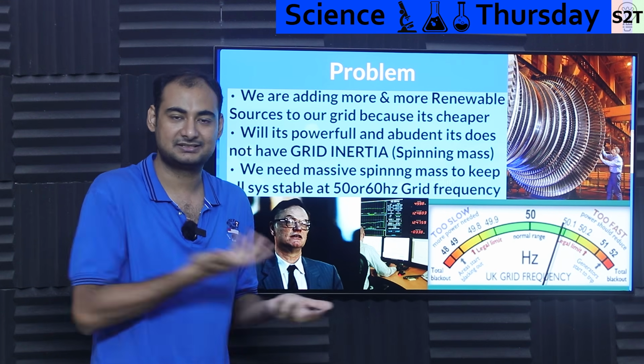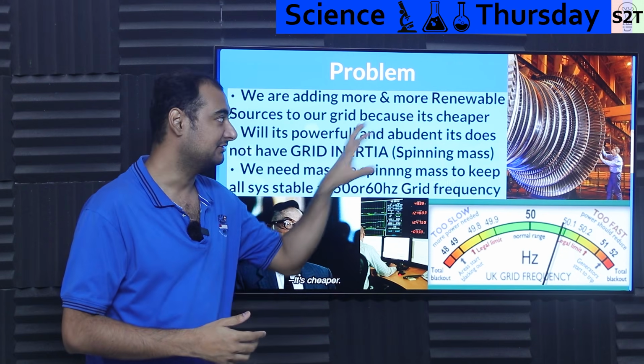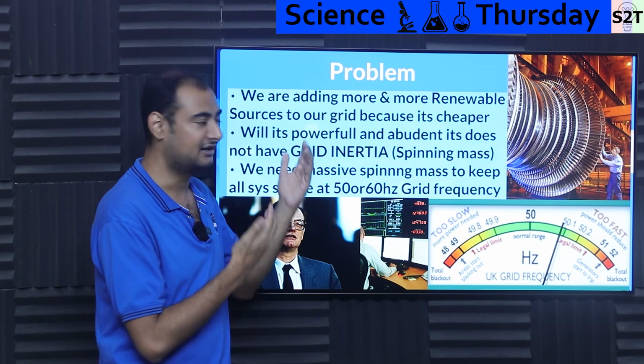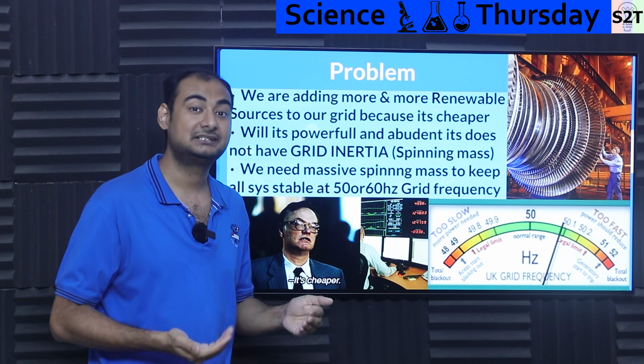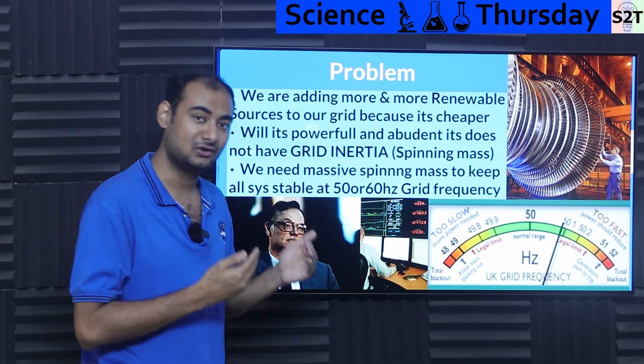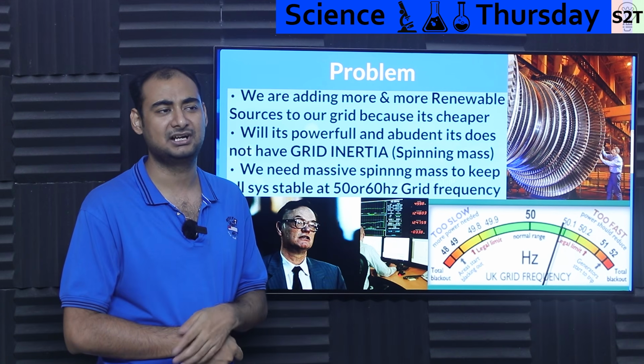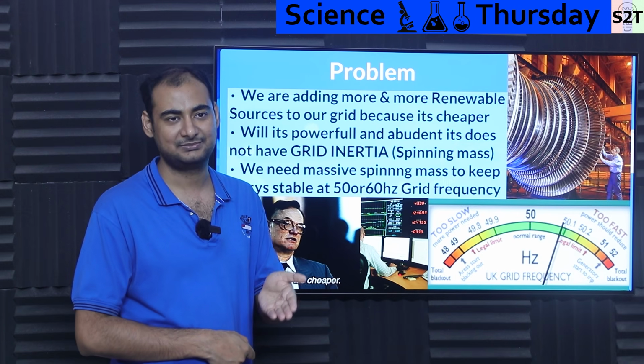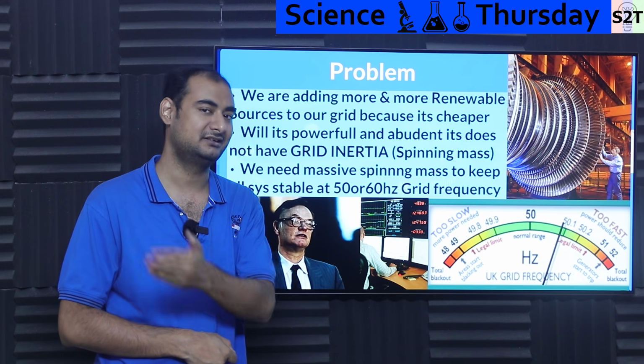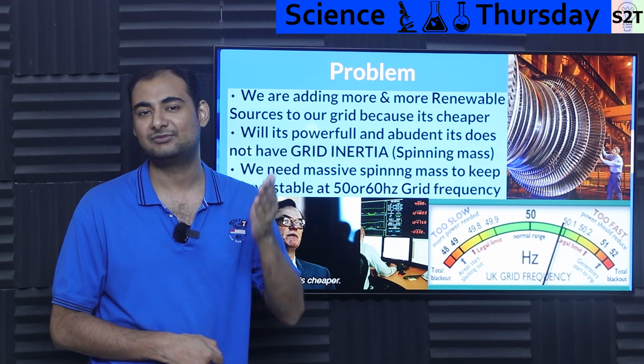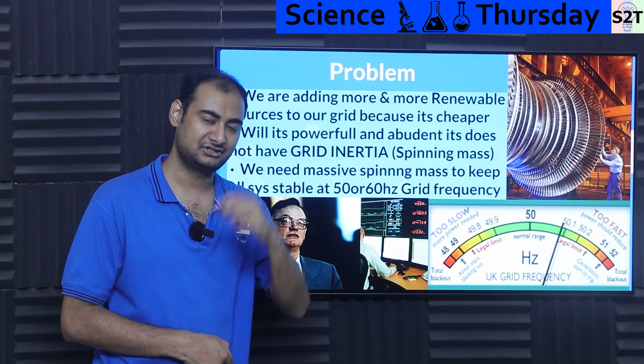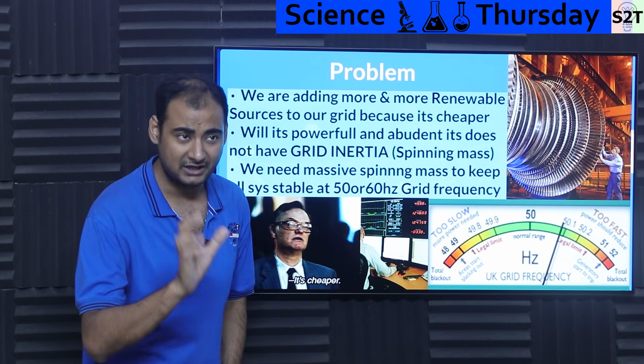It was like, bro, the resistance disappeared. Basically, the brakes failed, so it will start to speed up. But again, it is hundreds of tons, so it will take time to speed up. That is long enough that the steam valves will be like, bro, it's supposed to be spinning at 3000 rpm, it's starting to reach 3100 rpm, starting to reach 3105 rpm. It's like, yeah, cut the steam flow. And again, that's just one variable.